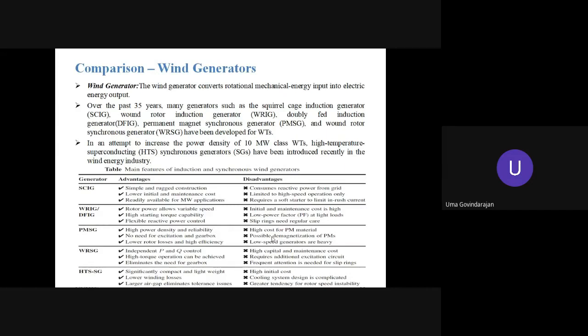Next, the third one is the PMSG, the permanent magnet synchronous generator, where the rotor has permanent magnets. The stator has a distributed winding, from where we can generate the power. The advantages are high power density and reliability, and no need for excitation or gearbox. It can be used for direct connection to the rotor of the wind blades, so you can eliminate the gearbox. That is one of the major advantages of PMSG.